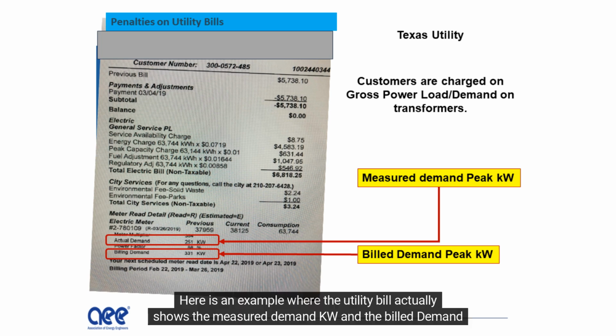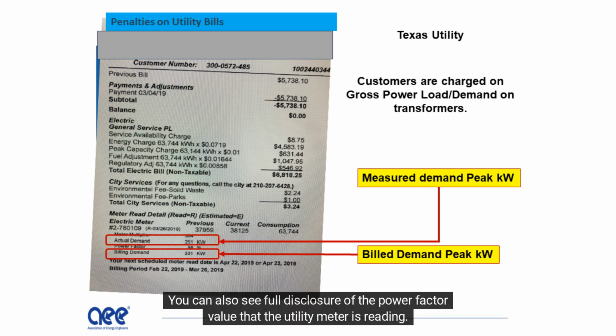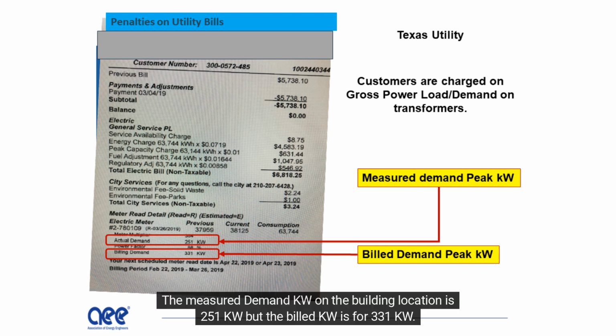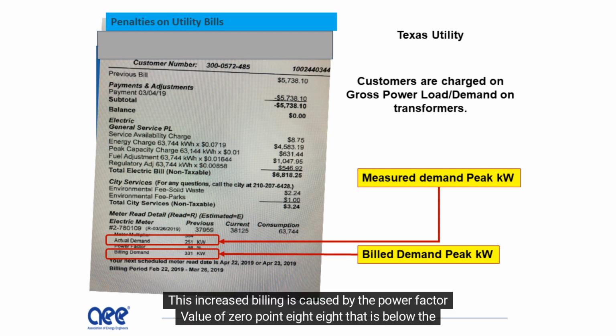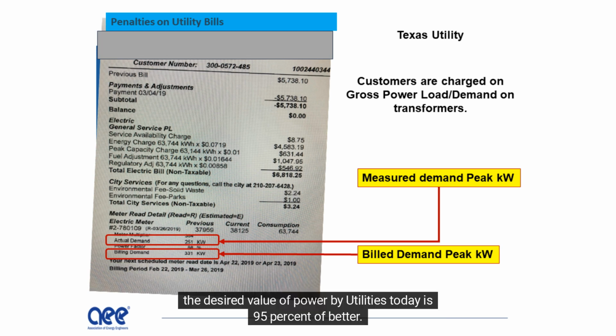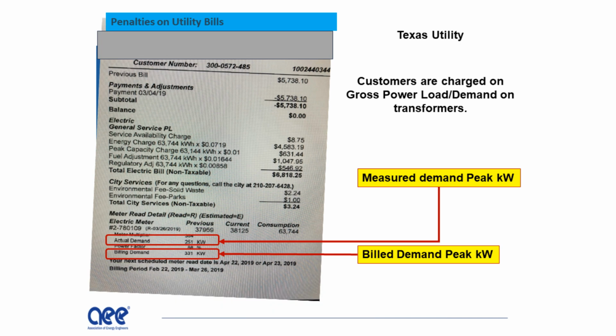Here is an example where the utility bill actually shows the measured demand kW and the billed demand kW. You can also see full disclosure of the power factor value that the utility meter is reading. The measured demand kW on the building location is 251 kW, but the billed kW is for 331 kW. This increased billing is caused by the power factor value of 0.88 that is below the desired value. The desired value of power factor by utilities today is 95% or better.